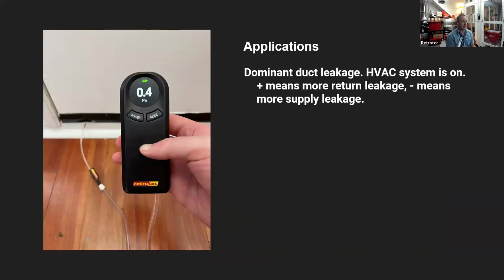Looking at house pressure, I talked about this earlier, seeing if a house is going positive or negative. So for example, if we have everything turned off in the house, and then we turn on the HVAC system, and if we see that the house is going positive, that likely means that we have more leakage on the return side of the system than we do on the supply side. And then vice versa, the other way around.